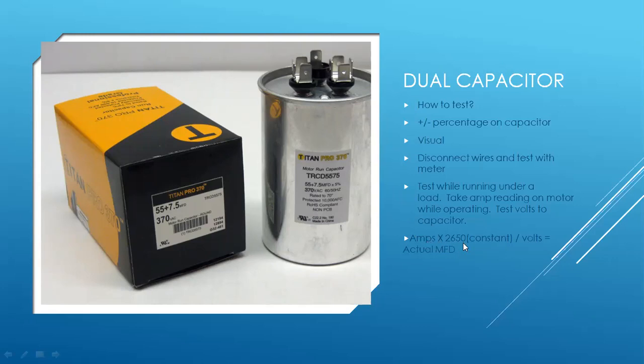So you're going to take your compressor amps times 2650, and you're going to divide that by your voltage. Now that's actual voltage. So if you're checking common to Herm, don't check your 208, 230, because it's going to skew your reading. So you want to check your actual volts. So you're common to your Herm terminal here. You take the amps times 2650 divided by the actual volts, and that will give you your actual microfarads under load. Many times the difference between testing like this with the wires off and under load can be sometimes dramatic. Sometimes there's no difference or it's close enough, but it's a good idea to have this in your bag of tricks, because you can do that once you have the unit back up and running, your coil's drying, you can do that check.